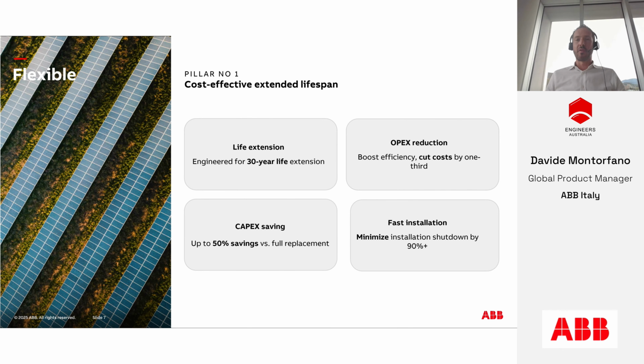In the key project, of course, we are considering everything, also the typical civil works that you need to do when you want to replace the full switchgears instead of applying a retrofit project. Let's go to the last one, which is fast installation. Definitely, retrofitting allows a very fast installation and commissioning, up to 90% less than the typical full switchgear replacement. Normally, a retrofit can be installed and commissioned in 1-2 hours, compared to 10-20 hours per panel when you do the full switchgear replacement.